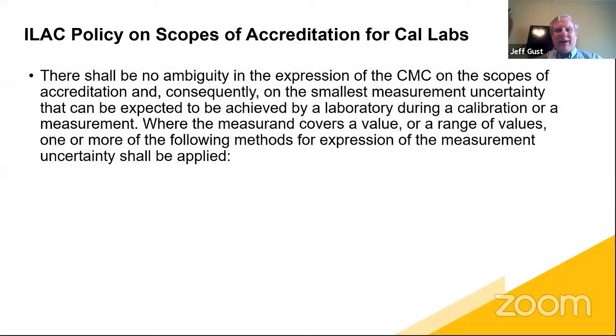And again, the real key on this is that there shall be no ambiguity in the expression of the CMC on scopes of accreditation, and consequently on the smallest measurement uncertainty that can be expected to be achieved by a laboratory during the calibration or a measurement. In other words, if you cover a range of values, then you might have to express uncertainty a little bit differently, which we'll get to in a minute. But the key is that whatever measurement you would expect the calibration laboratory to perform, you should have a pretty unambiguous understanding of what their calibration measurement capability is at that point.